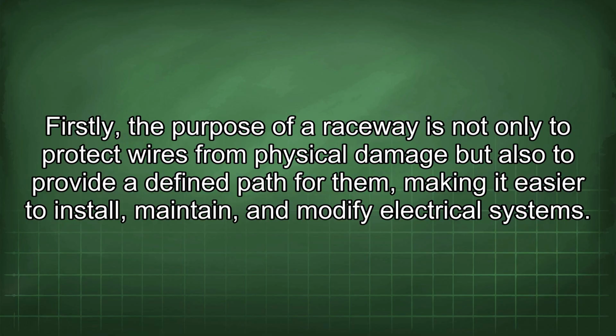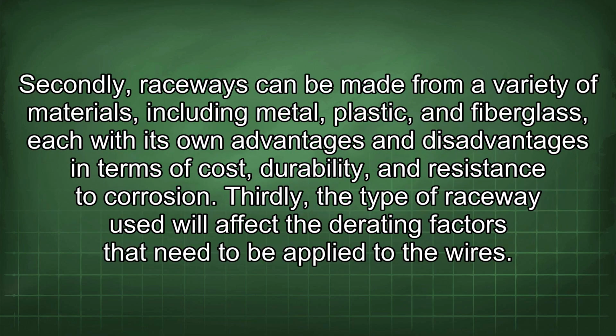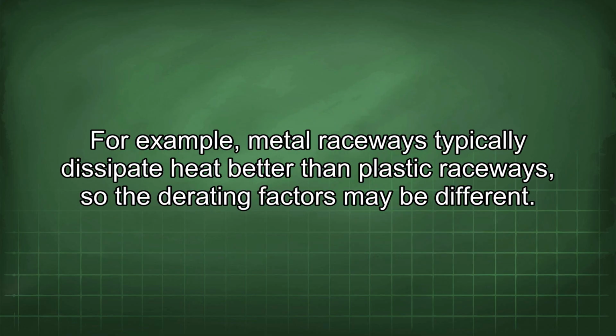Firstly, the purpose of a raceway is not only to protect wires from physical damage, but also to provide a defined path for them, making it easier to install, maintain, and modify electrical systems. Secondly, raceways can be made from a variety of materials, including metal, plastic, and fiberglass, each with its own advantages and disadvantages in terms of cost, durability, and resistance to corrosion. Thirdly, the type of raceway used will affect the derating factors that need to be applied to the wires. For example, metal raceways typically dissipate heat better than plastic raceways, so the derating factors may be different.